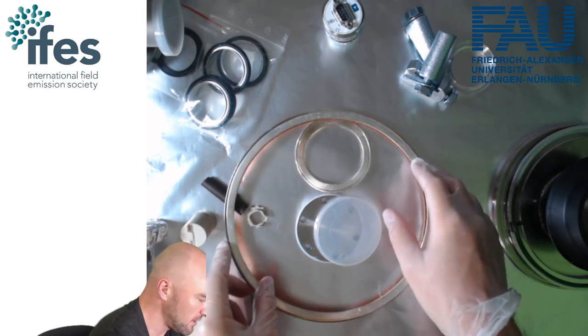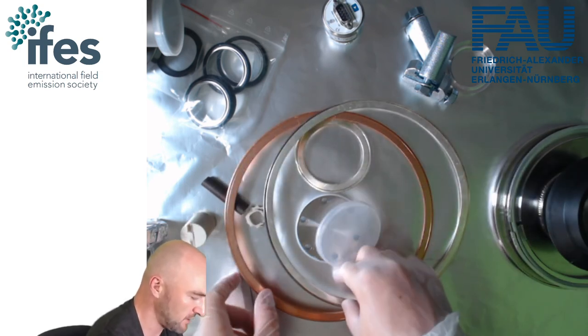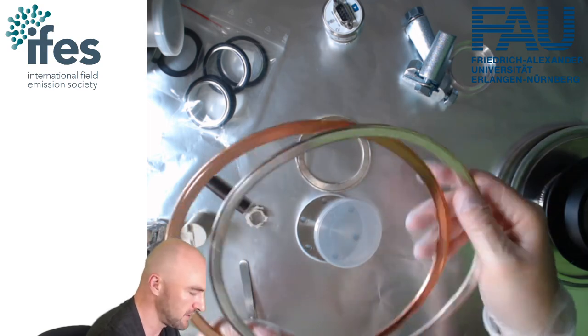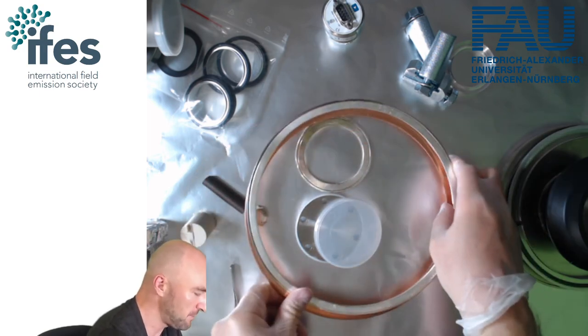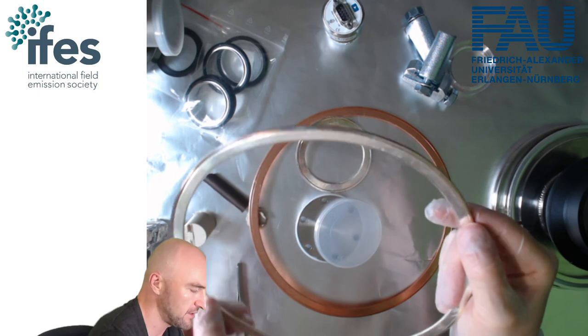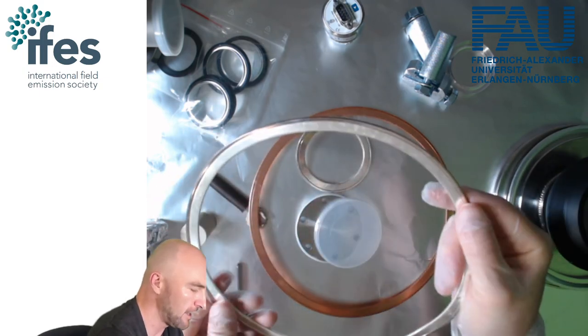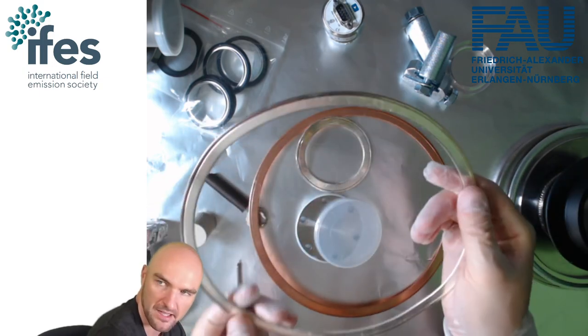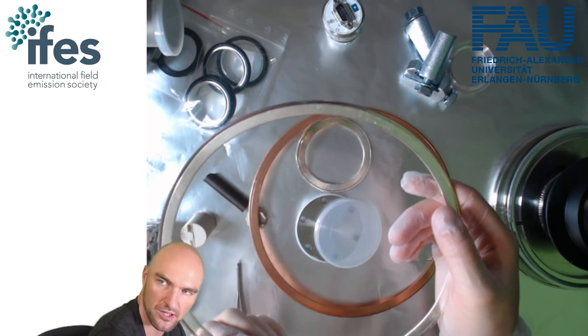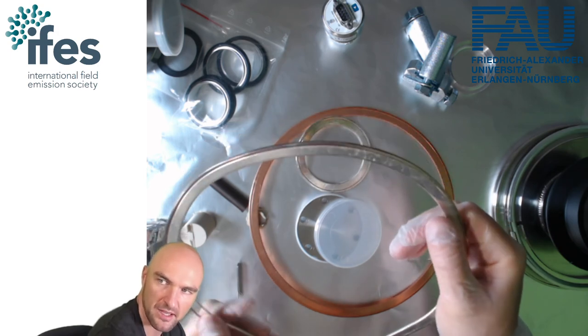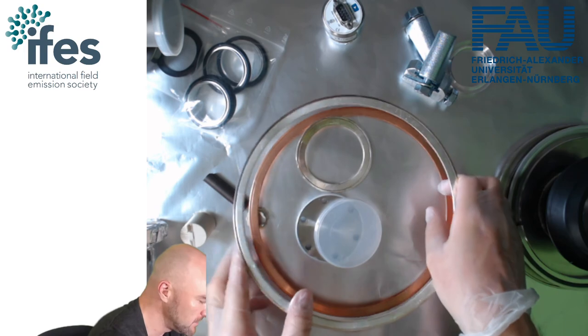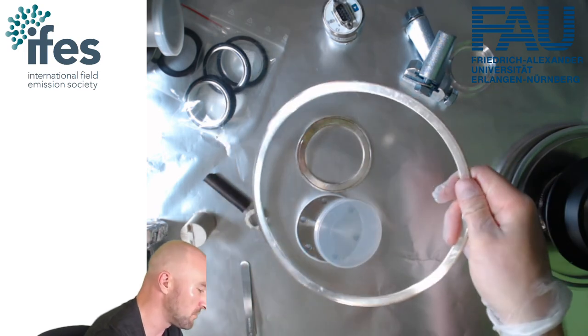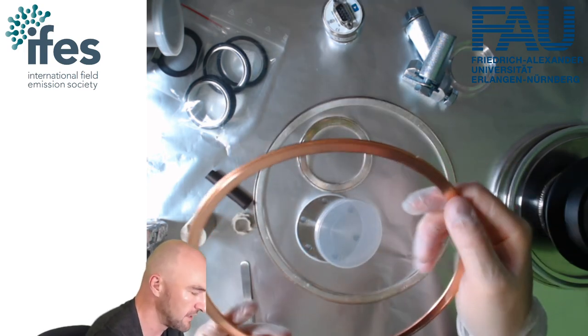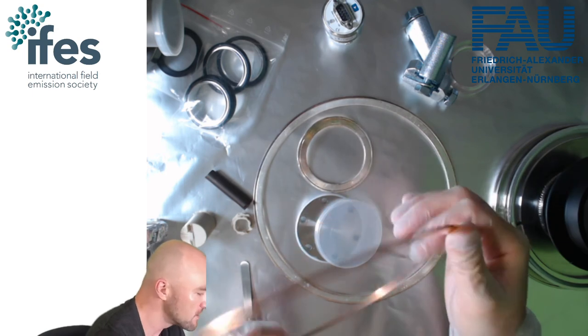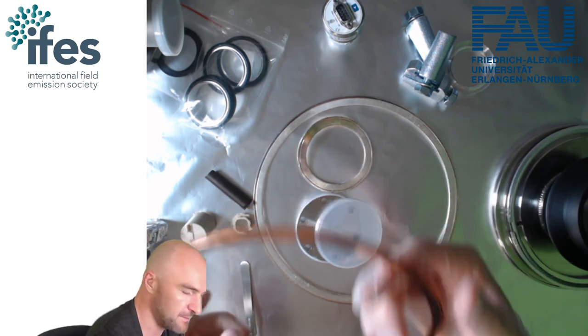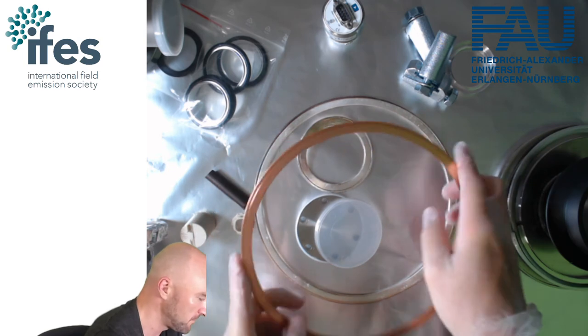And the reason for the different kinds of seals is that if you bake to very high temperatures, the silver helps the gasket to not stick to your ultra high vacuum parts. Okay. If you have only copper and you bake to very high temperatures, you might get the copper sticking to the stainless steel a little bit. Right? Unless you bake to very high temperature, that's not actually much of a concern.